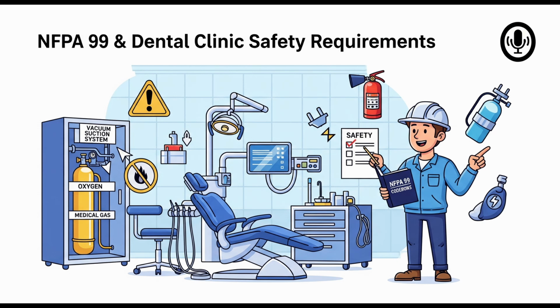It's crucial. If stainless steel tubing is used, which is less common in dental but allowed, it requires specific orbital welding techniques and qualified welders. There are also some newer joining methods mentioned, like axially swaged fittings, but brazing with a nitrogen purge is the gold standard for copper medical gas lines.